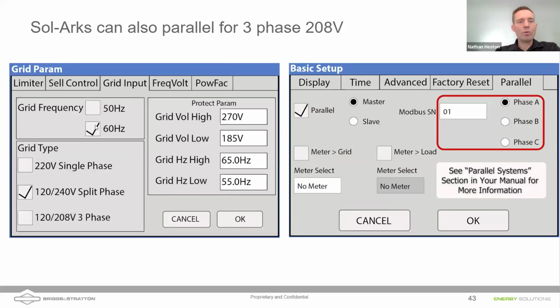Under the grid input, most typically you're going to have 60 hertz if you're here in Canada, Mexico, or the US. 120, 240 split phase is the typical power that we draw here. However, these inverters can be used with three-phase systems. You can use a single inverter to do 2 of the 3 phases. You can use 2 inverters to do 3 phases, but then they wouldn't be balanced.